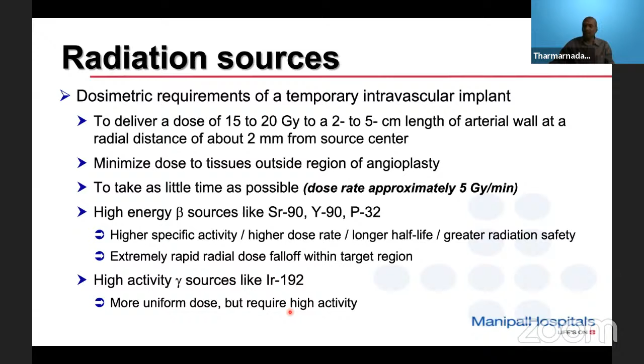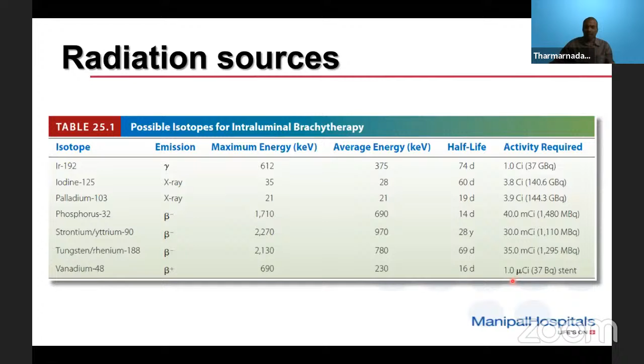What you have to note down is the vanadium 48 beta source emitting 230 average keV with a half-life of 16 days. It's a permanent implant in the form of a radioactive stent, and that requires only an activity of 1 microcurie. Just 1 microcurie is all that is required. So that means that practically there is no radiation safety issue at all with this type of permanent radioactive stent implant.